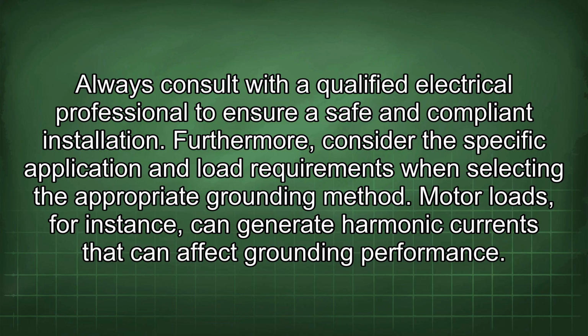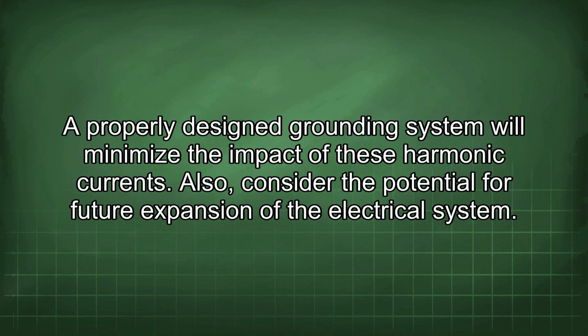Furthermore, consider the specific application and load requirements when selecting the appropriate grounding method. Motor loads, for instance, can generate harmonic currents that can affect grounding performance. A properly designed grounding system will minimize the impact of these harmonic currents. Also, consider the potential for future expansion of the electrical system.